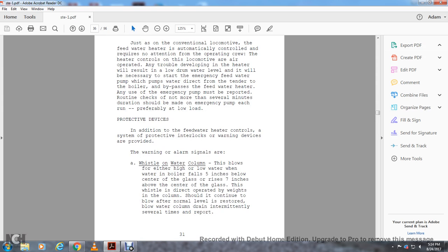Protective devices. In addition to the feed water heater and the control of the system, protective interlocks and warning devices are provided, with a warning alarm signal system and the whistle on the water column. This sounds when the water is either high or low, when the boiler falls 5 inches below the center of the glass or rises 7 inches above the center of the glass. This whistle is directly operated by the weights in the column.